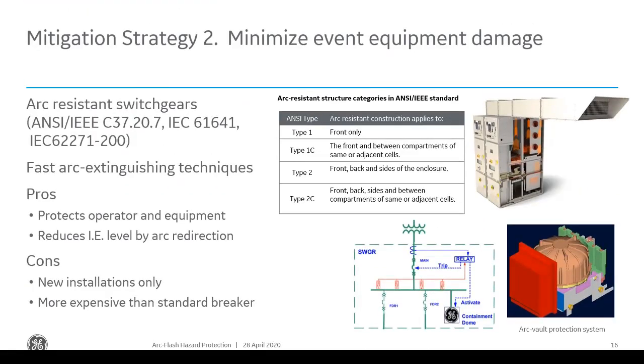So yeah, that's a good question. Obviously, if it's designed properly for the incident energy, if the incident energy is what it's defined for, it should not cause any damage to the equipment itself, because a lot of that pressure should be vented properly. But obviously, it all depends on whether it's designed properly. That's very important. That's why it's sometimes very difficult to size these for arc flash, and even cost prohibitive. If you have a lot of arc flash incident energy, it might be cost prohibitive for somebody to build you something that will be able to vent all of that pressure safely.